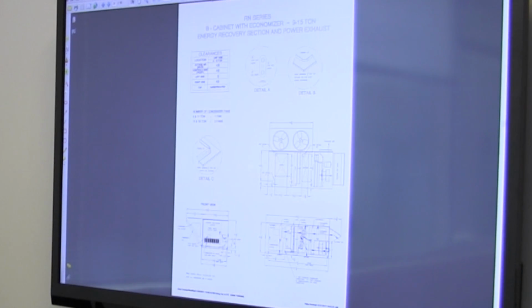Again, there's an extensive terminal strip. This one has your compressors, and for every compressor there is an enable-disable point, and there is a 0 to 5 volt capacity point for every compressor. Beyond the compressor and the reversing valve for the heat pump, it's essentially the same points as you see on the other unit. Smaller unit, got 2 condenser fans.